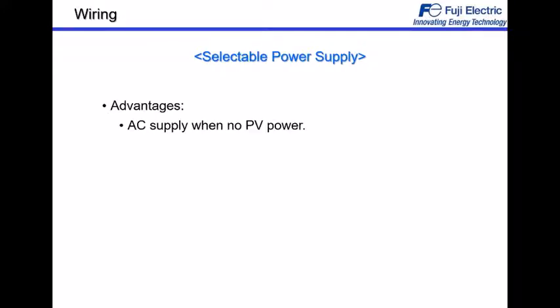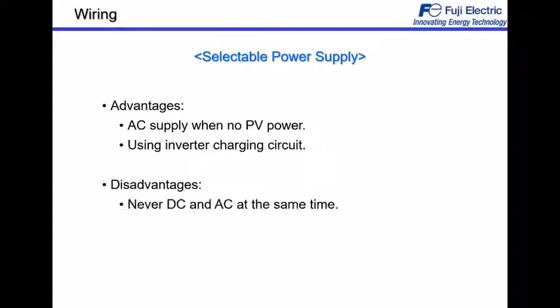Advantages of the system: AC supply when there is not enough photovoltaic power, so we can always switch if there is not enough power. It also uses the charging circuit of the inverter as a protection. It has some disadvantages. We cannot have DC and AC at the same time with this system. We select photovoltaic or AC power. An external sequence is needed, so we need an automatism that makes the switch.